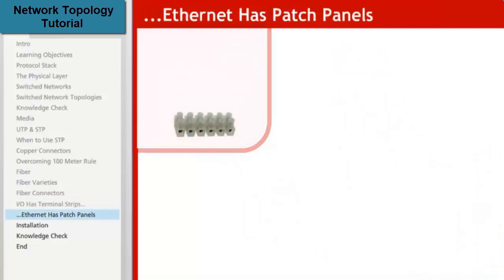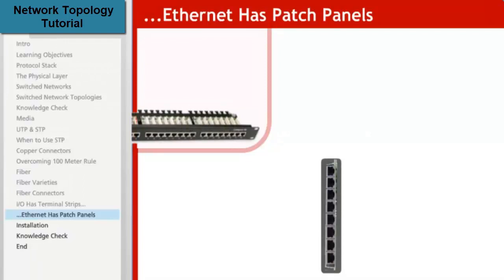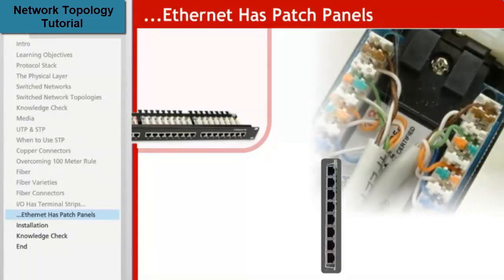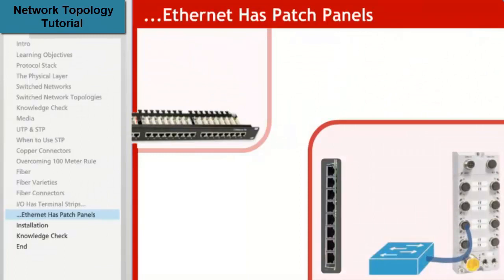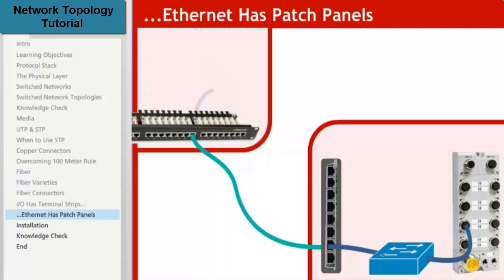A similar concept is used when constructing a physical Ethernet channel. In the previous example, terminal strips are used to connect to the discrete field devices. In Ethernet installations, patch panels, which are passive devices, are used to provide the same type of functionality. Patch panels are designed for copper or fiber connections with two sets of connections for each circuit, just like on a terminal strip. There are a variety of termination methods, depending on the patch panel manufacturer and the application requirements. Some require that cables be terminated with connectors and simply plugged into the correct mating connector, and others secure the individual wires of the connector directly to the patch panel itself. In this example, a copper patch cable is used to connect the distributed I.O. to a switch in the same enclosure. The switch is connected to a patch panel by a fiber patch cable. Then a long run of fiber can be made to the main panel. When the fiber enters the panel, it will be terminated at a patch panel again. Another patch cable will connect the patch panel to the switch.